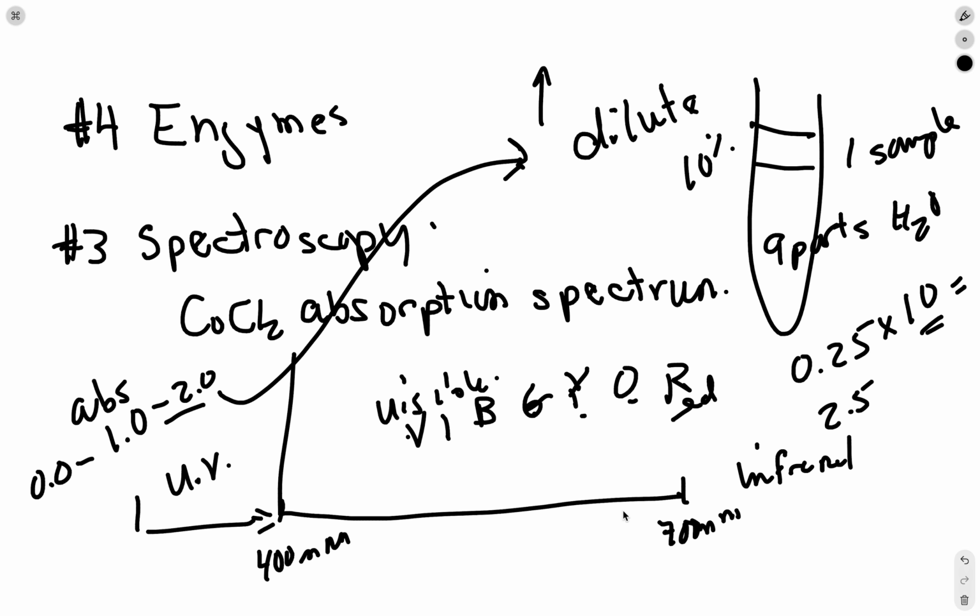There are lots of biological molecules that absorb out here, proteins, DNA, RNA, and some that absorb out here, some other types of biological molecules. Our instruments just use the visible wavelength. It's possible to have an instrument that can also measure in the UV or infrared. They just need a different light source and a different range of wavelengths to measure.